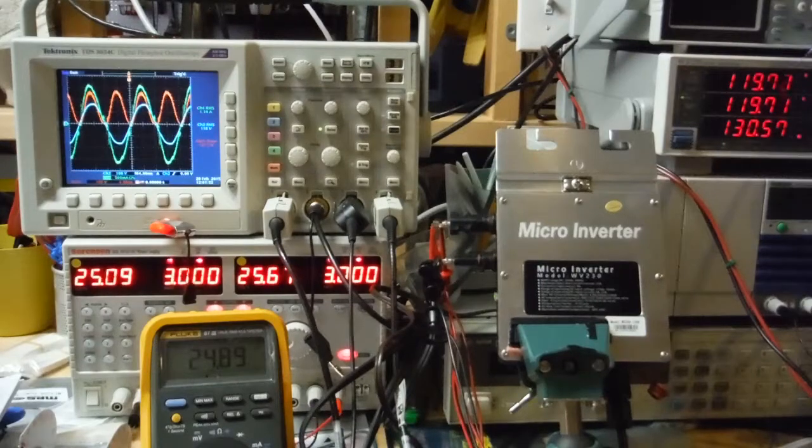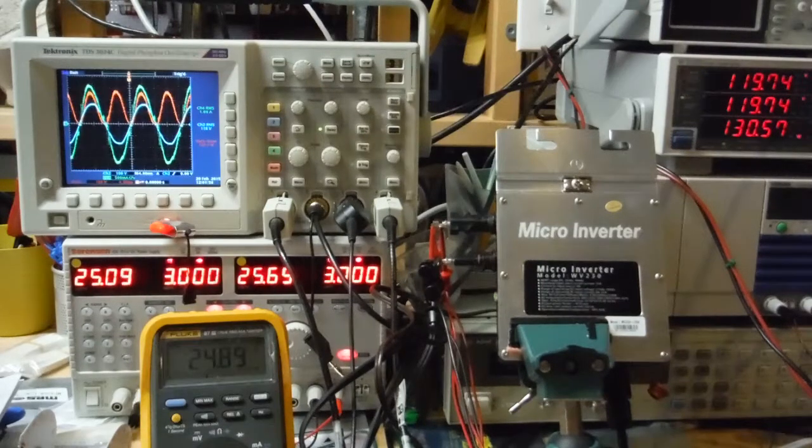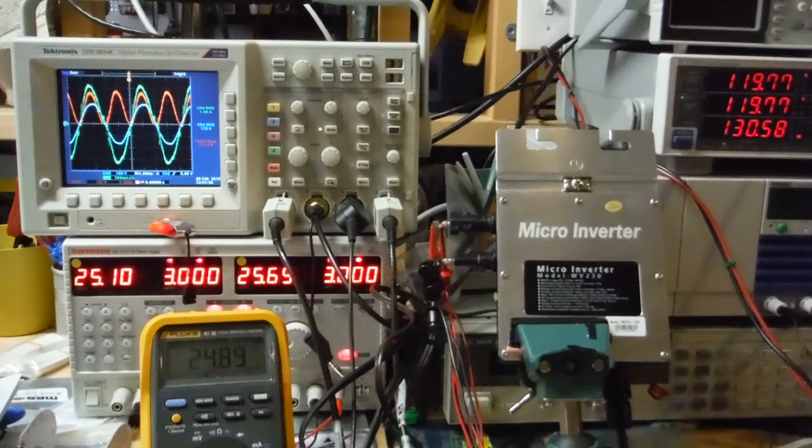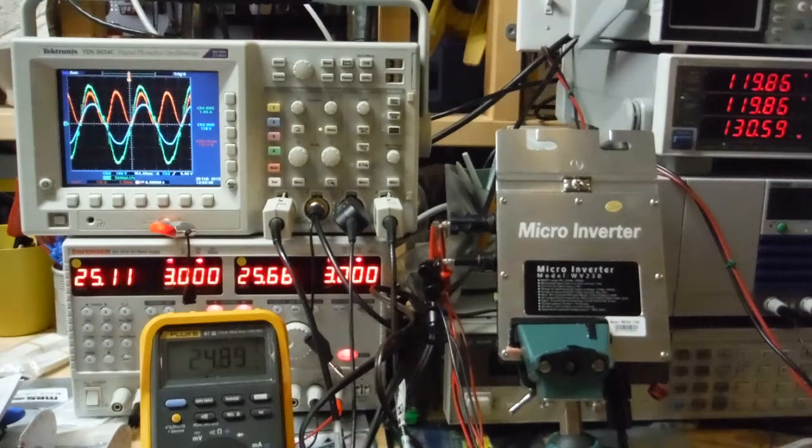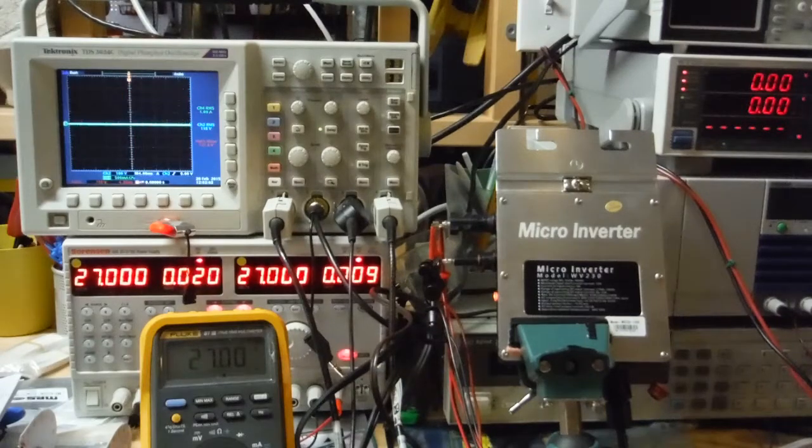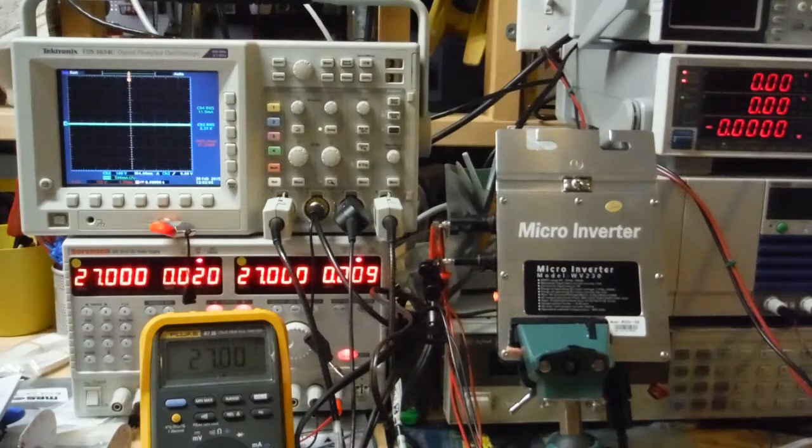So right now, there's 120 volts at the output of this guy. If I unplug it from the grid, even though I still have input voltage, it should shut that down. And it does. So the islanding protection works.